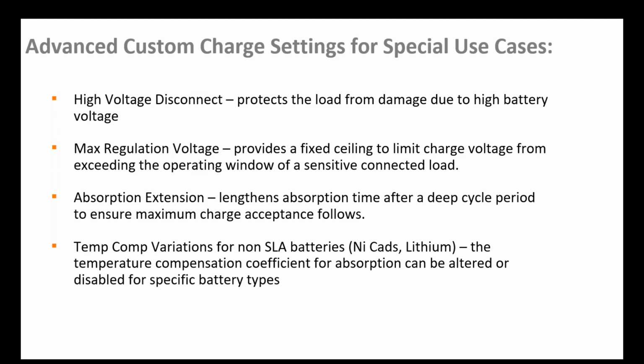Absorption extension is usually more of a useful feature for lead acid batteries, where the absorption duration really varies with the depth of discharge the previous day. So if you were exercising the battery very heavily the day before, you got to a very low capacity, and you want to recover it the next day, it would trigger the absorption extension time interval to override the length of absorption for that day to try and recover any lost capacity from that deep discharge.